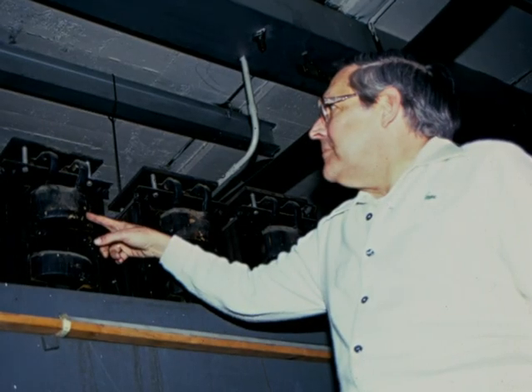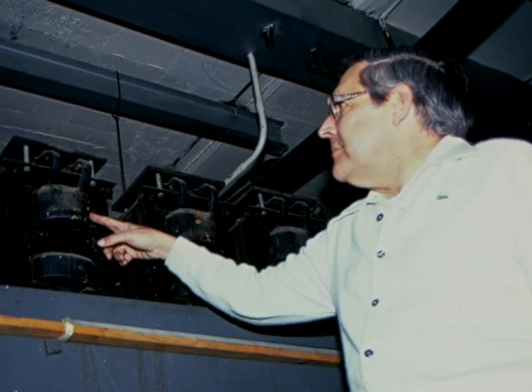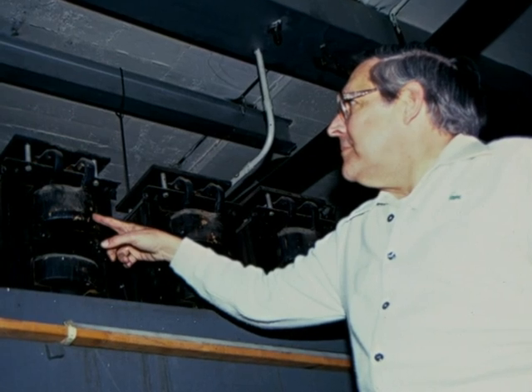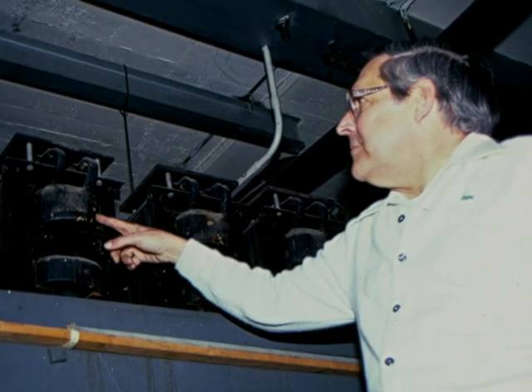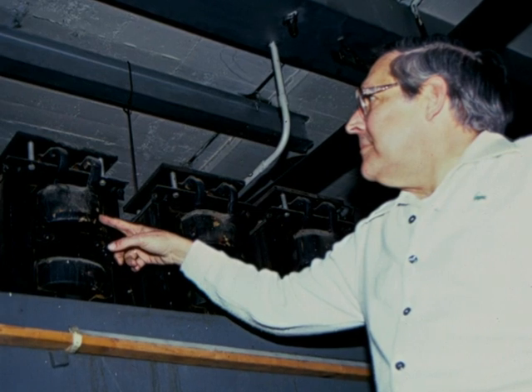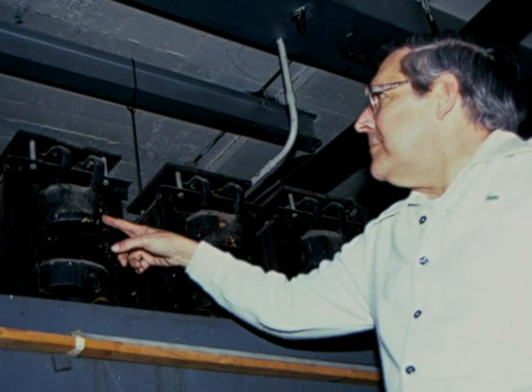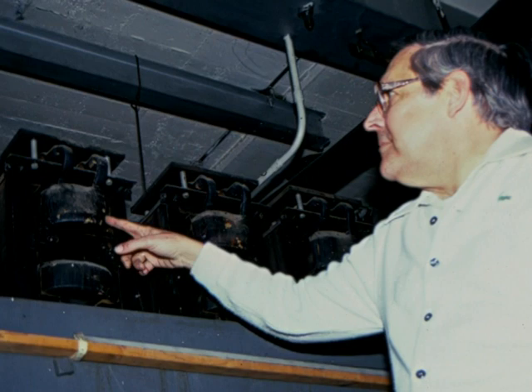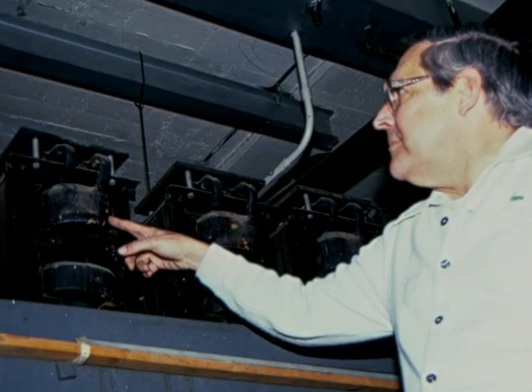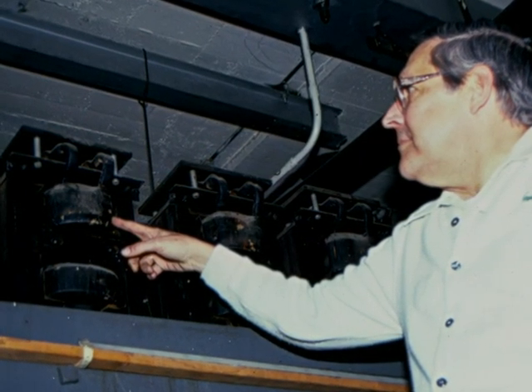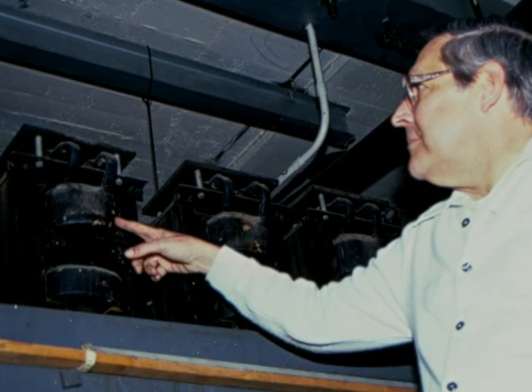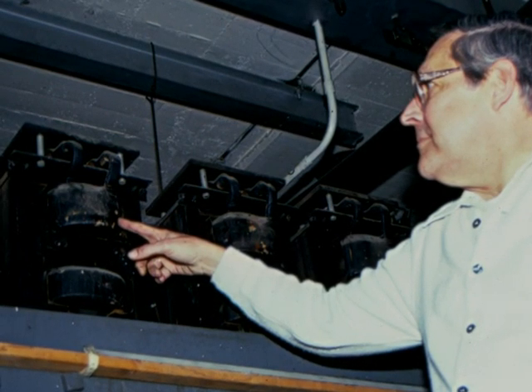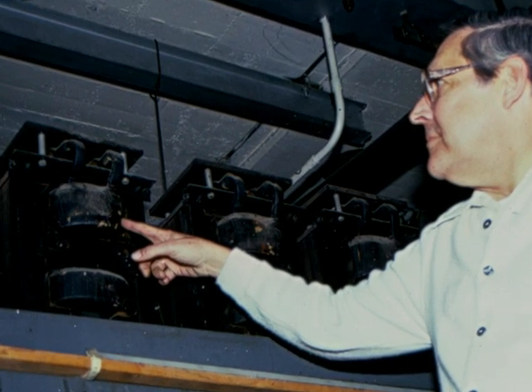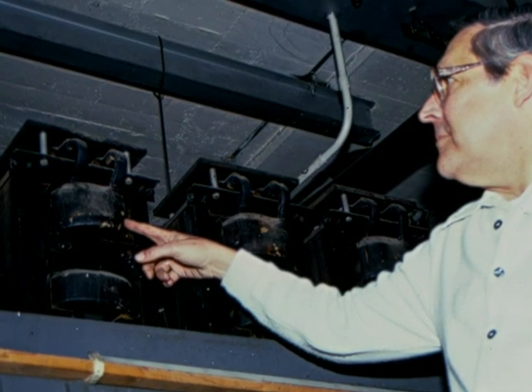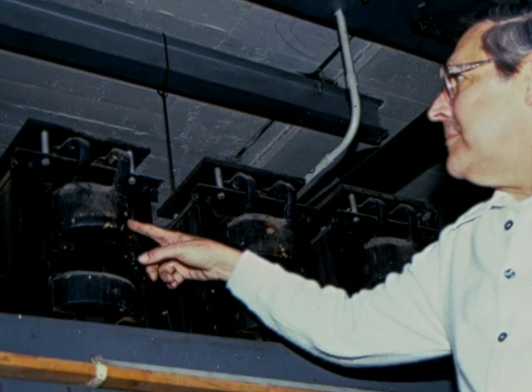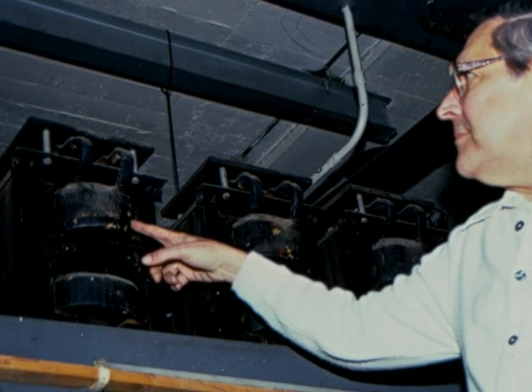The AC filaments of each 898 required 3 single-phase, high-reactance transformers with 240-volt primary and 16.5-volt, 140-ampere secondary. The transformers were designed with high reactance to limit the startup current to 200 amperes with cold filaments. Each transformer was 13 inches high, 10 inches wide, 8 inches deep, and weighed over 150 pounds. The secondaries were wound with copper conductor, 3/4 inches wide and 1/4 inch thick.